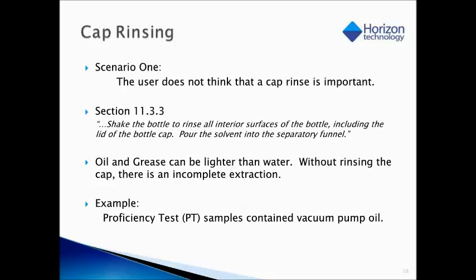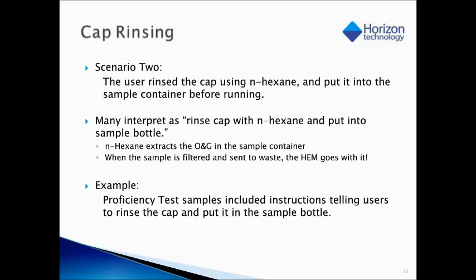I think everybody gets the importance of why you would need to rinse the cap, but the other thing that needs to be mentioned is the technique for how you're going to rinse that cap. Most older instructions, including some instructions that come in with proficiency tests even now, tell users to rinse the cap with hexane and then put it back in the bottle and then extract the sample.